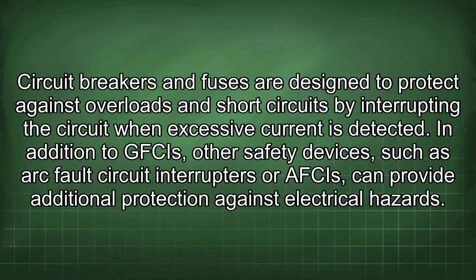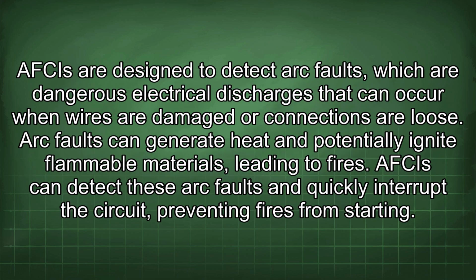In addition to GFCIs, other safety devices such as arc fault circuit interrupters, or AFCIs, can provide additional protection against electrical hazards. AFCIs are designed to detect arc faults, which are dangerous electrical discharges that can occur when wires are damaged or connections are loose. Arc faults can generate heat and potentially ignite flammable materials, leading to fires. AFCIs can detect these arc faults and quickly interrupt the circuit, preventing fires from starting.